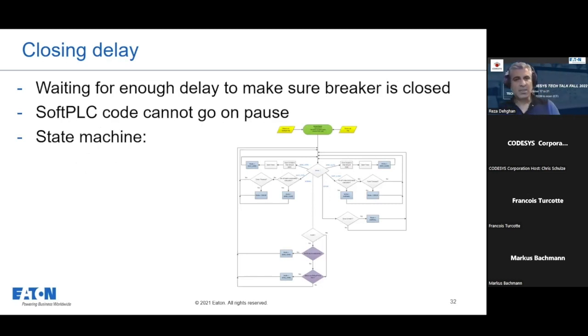Yeah, so a little bit later, we decided to get the confirmation for open commands and for close commands, and it led to the concept of, first of all, waiting for enough delay to make sure the breaker is closed or open. As we said, soft PLC code cannot go on a pause. So we decided to come up with a state machine. The whole idea of the state machine is that it sends a command and then it just loops in a waiting loop. So every time it goes back to the condition, it checks the status. In this state machine, I think we have 5 or 6 different statuses.